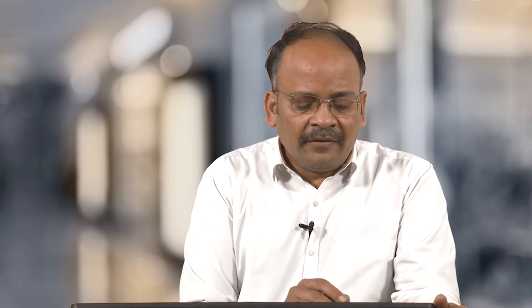For continuous operation, the biomass solids generated in the aeration tanks are separated and thickened in the secondary clarifier via gravity settling. A portion of the settled solids — called secondary or activated sludge — is recycled and returned to the aeration tank, and the excess sludge is withdrawn from the clarifier underflow for additional handling or disposal. The clarified liquid, which is the treated final effluent, is further disposed of into a stream or taken for further treatment depending on requirements.